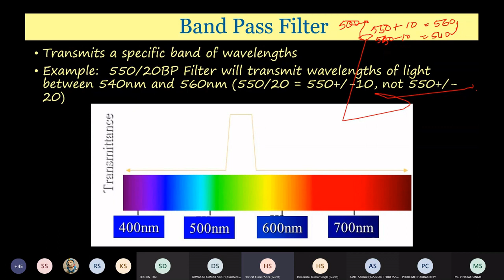So these are the filters. Now next, we use dichroic filters. They actually turn the light. Dichroic filters can also be long pass, short pass, as well as band pass. If I want to turn the light, I will use the dichroic mirror. Suppose this is a 550 short pass. Below 550 everything will go to the detector. All above 550 will go here, because it will reflect everything above that particular wavelength. Depending on the specs of the filter, some of the light is reflected and part is transmitted, as I showed you. If it is a 550 long pass, it will allow everything above 550, and everything less than 550 will be reflected. So now you got this idea.